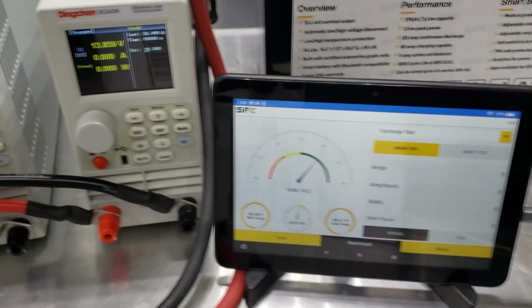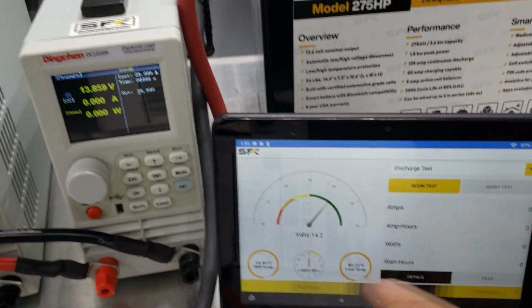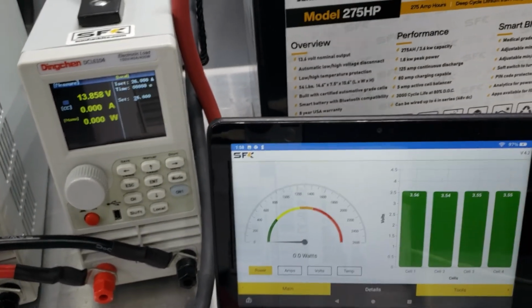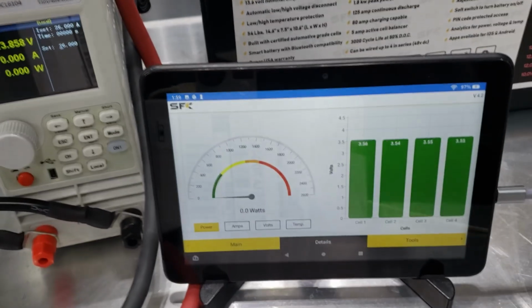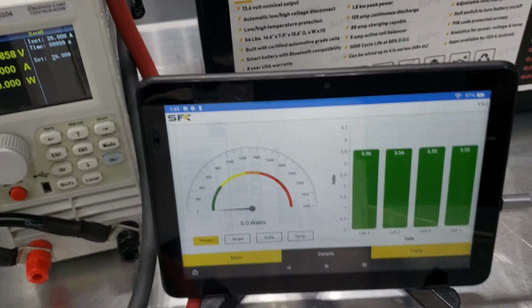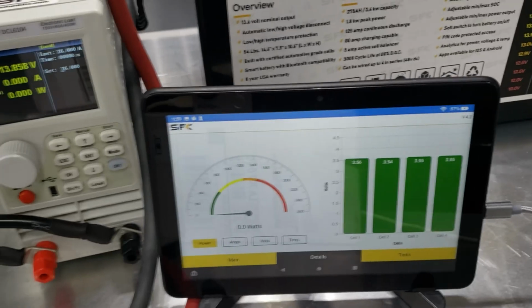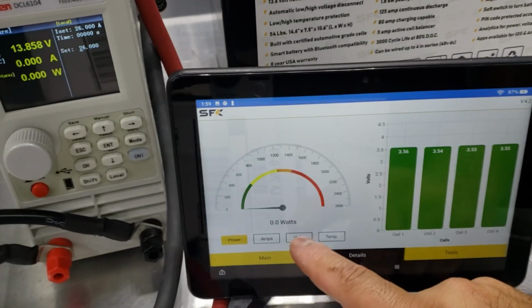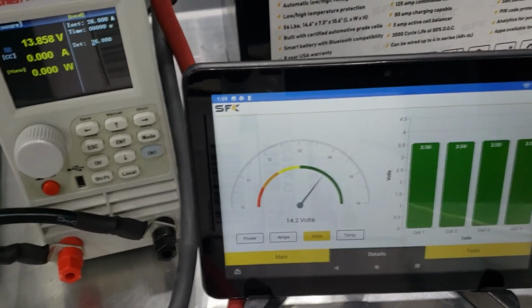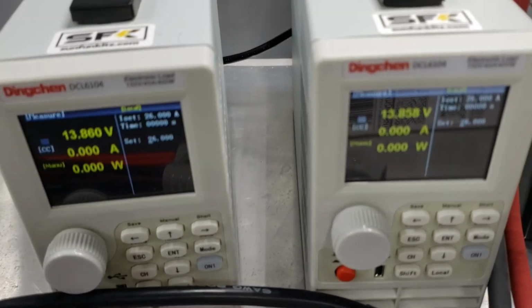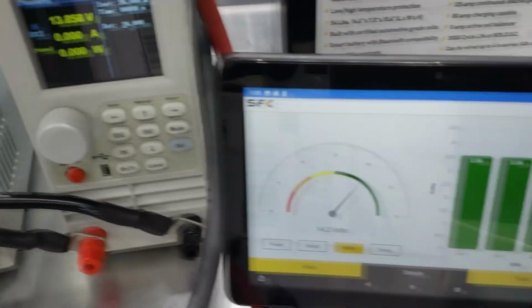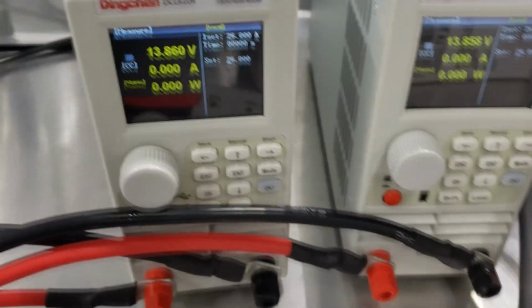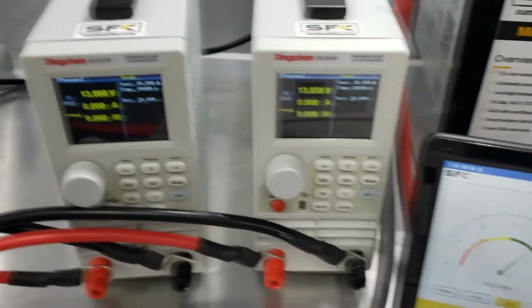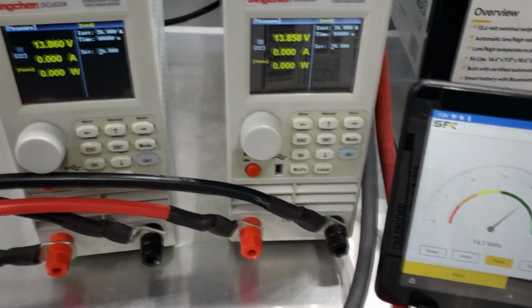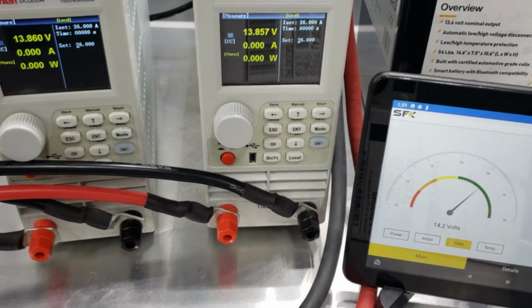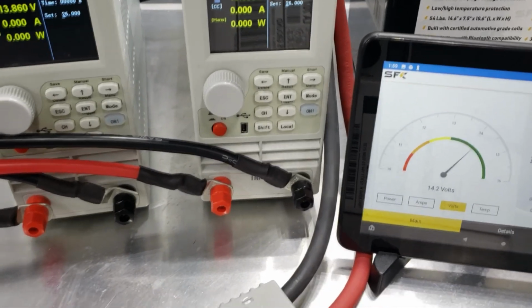We also want to look at the details and make sure everything's fully charged. Here all our cells are at 3.56, 3.54, 3.55, pretty well balanced, and the total voltage of the battery is around 14.2 volts. You'll notice a slight difference between this voltage reading and the 10 volt cutoff setting, so it'll be accurate for the most part, but you may have a few amp hours it won't detect because of that voltage difference.